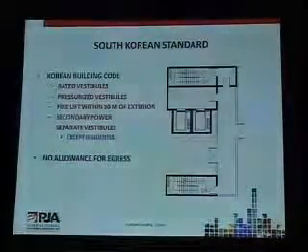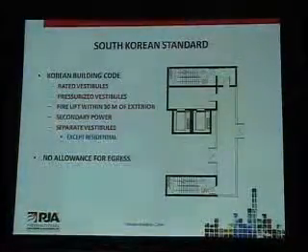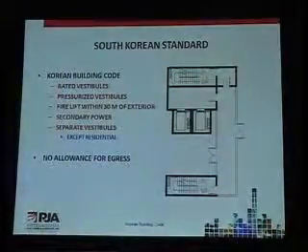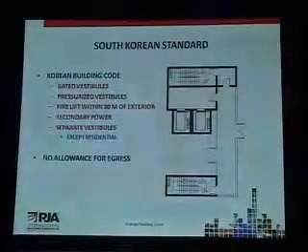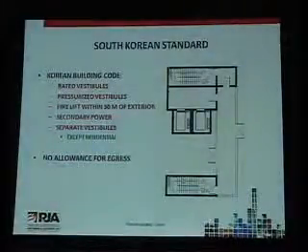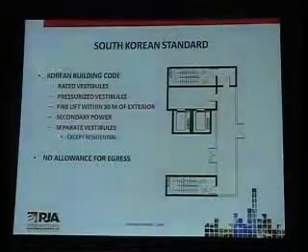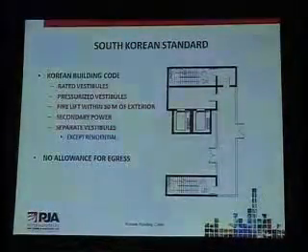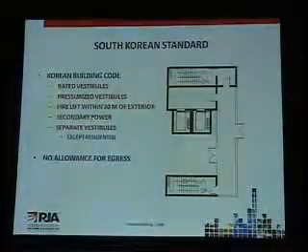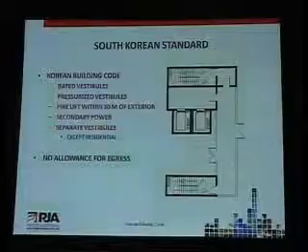And now we get to the South Korean standard. Again, very similar. You can kind of see that the layout's getting the same. But there's a fairly unique requirement in this: they actually restrict you from sharing a vestibule. You are not permitted to share a vestibule except in residential buildings. So that's something that's quite unique. But again, you still see some similar requirements: a rated vestibule with 30 meters to the exterior for the fire lift, and secondary power. They do require provisions for some form of smoke protection, usually accomplished by pressurizing the vestibules. Again, no allowance for egress.